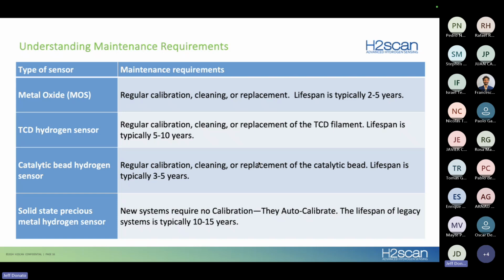Where we get into a little more complexity is if it has to be calibrated. For instance, a catalytic bead system may need to be calibrated every 6 to 12 months. If you have to calibrate that, that's another maintenance action the customer has to take. Whereas TCDs, a lot of times, will last the full 5 years without having to be calibrated. And then precious metal sensors actually have algorithms inside so that they calibrate themselves. They auto calibrate, or self calibrate, and they have a system life expectancy of 10 to 15 years.